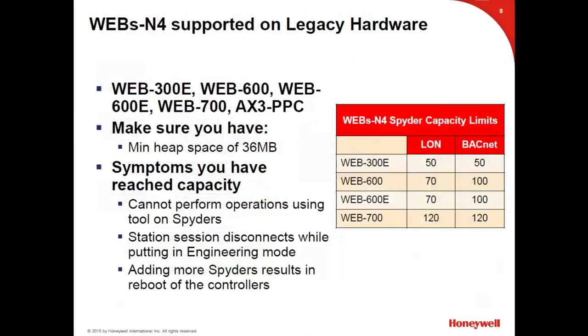This slide is specific to Honeywell. If a contractor reaches the point where they want to upgrade existing AX JACEs to Niagara 4, you can actually push Niagara 4 software into an AX JACE, but there are limitations. A Niagara-certified contractor needs to verify these requirements — the main one being that heap space must be 36 megabytes. The slide also shows how many spider controllers each AX JACE can handle in the N4 version. A lot of times people say the old hardware just needs to be replaced.